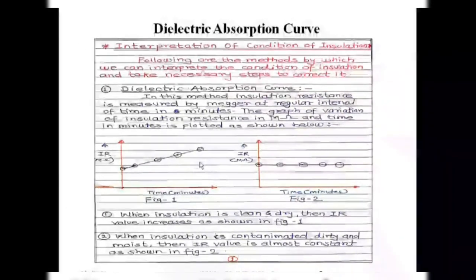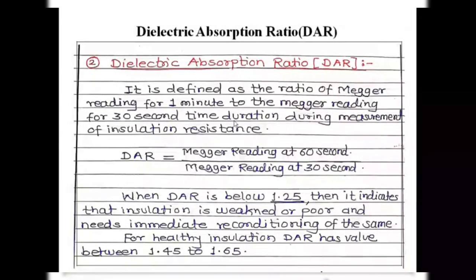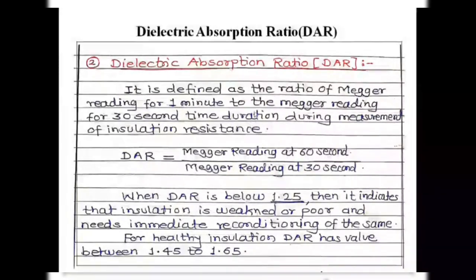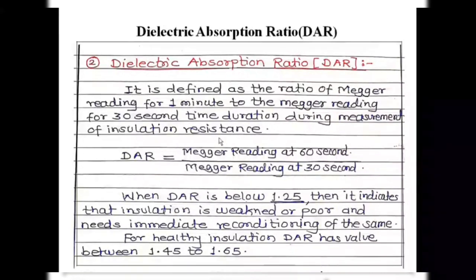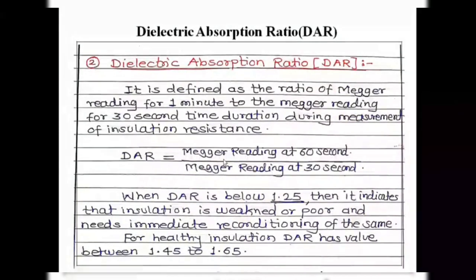The next method is the dielectric absorption ratio (DAR). It is defined as the ratio of the megger reading at 1 minute to the megger reading at 30 seconds during measurement of insulation resistance. Mathematically, DAR equals the megger reading at 60 seconds divided by the megger reading at 30 seconds after the start of the test.